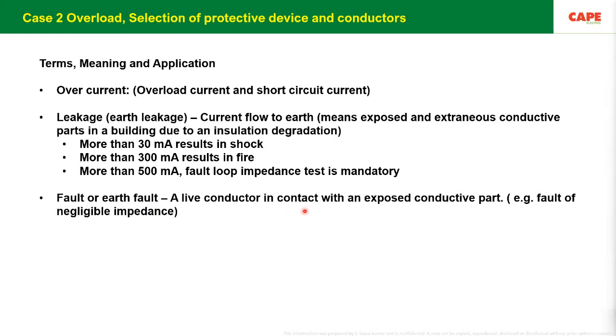It means a live conductor is in contact with an exposed conductive part. That means the impedance, the resistance between the live conductor and the earth, meaning the body of the equipment, is quite low. As a result, a person who is touching it may get an electrocution, may get a shock. So basically, overcurrent, leakage, and fault are 3 distinct safety measures. We should always keep this in mind and select the appropriate protective measure.